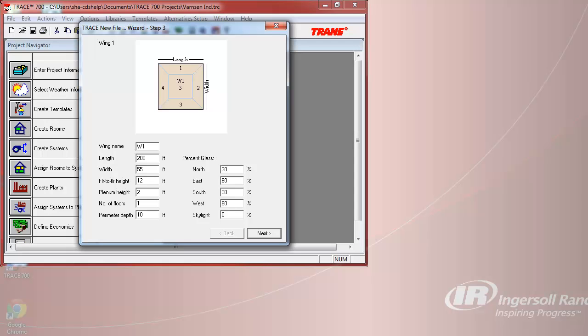To model the 15 stories of the building, we would want to change the number of floors to 15, as well as input a perimeter depth of 15 feet. Perimeter depth should typically not exceed 25 feet, or this can impact the envelope losses.